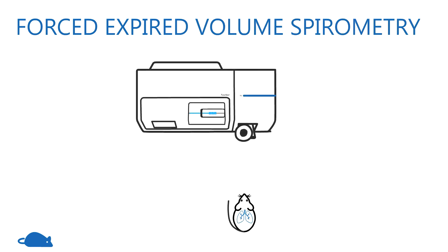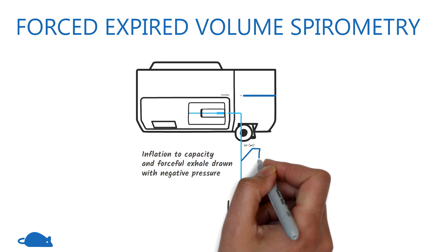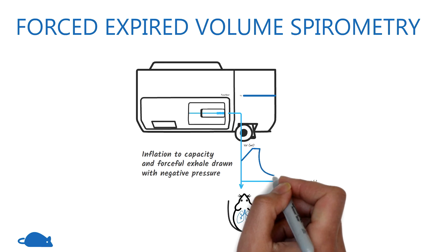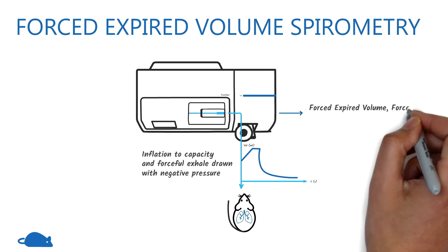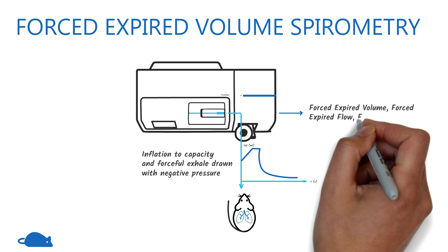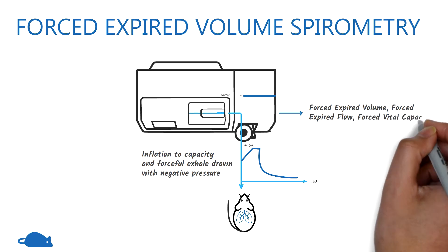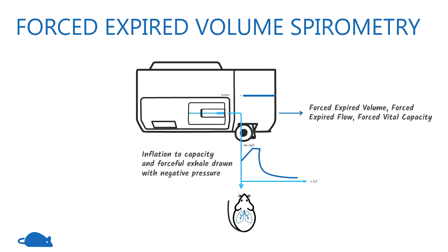In the forced-expired volume measurement, the lungs are recruited to total lung capacity and then a forced expiration is elicited with exposure to a negative pressure. This allows the flexiVent to calculate spirometry-like measures such as forced-expired volume, forced-expired flow, and forced vital capacity.